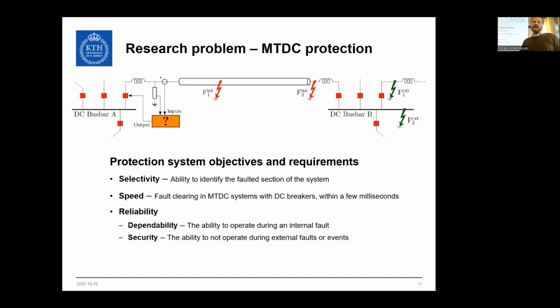Then we come to the most difficult question, I would say: reliability, which you can divide into dependability and security. Dependability is that the protection is able to detect the fault. It also means the protection should operate even during strange scenarios you could not even think of—everything has gone wrong, but it should still operate. Then you have the opposite, security: even if you get some strange disturbance, the protection should not operate in that case.